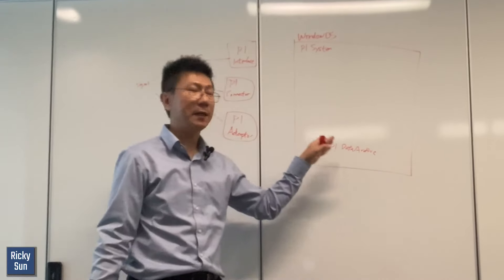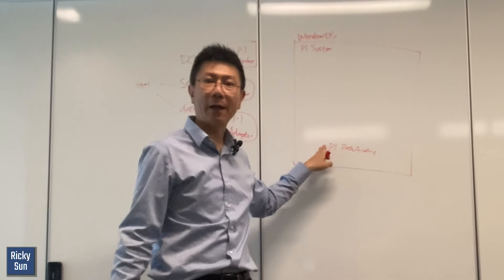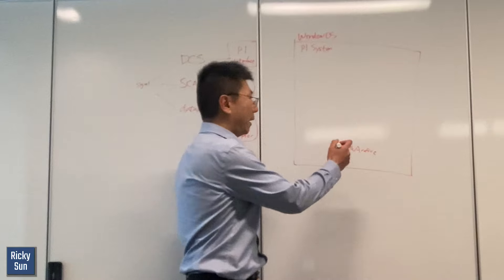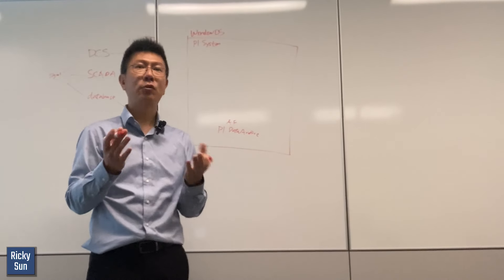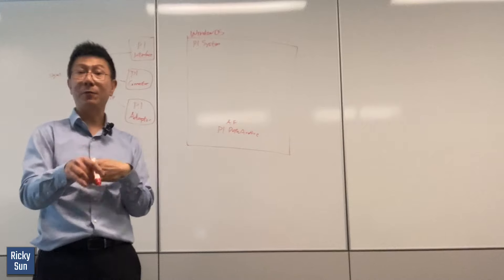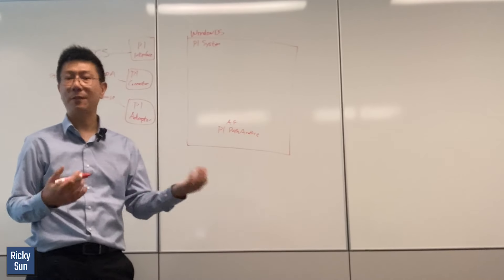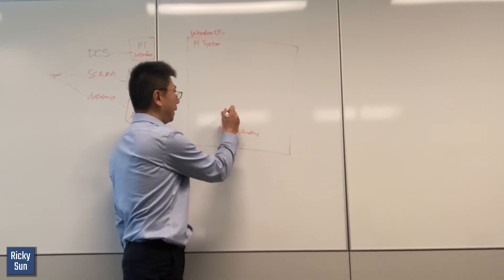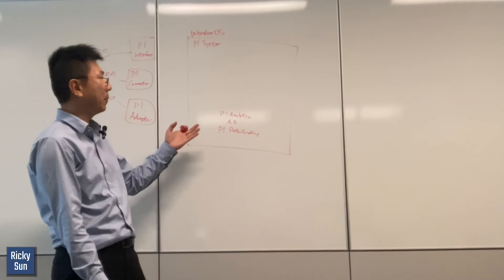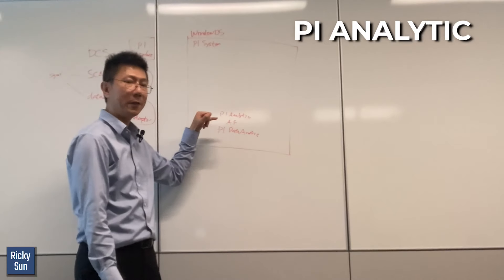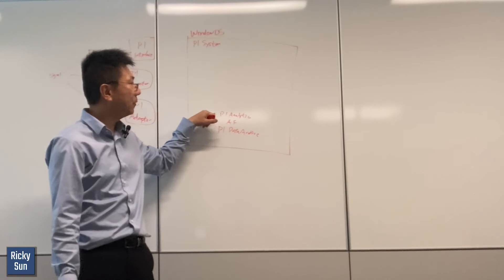The interface, connector, or adapter is responsible for sending the data to the Data Archive — the timestamp and the value. Then we have AF, the Asset Framework. AF lets you structure your data so you can find it more easily. You can create a customizable hierarchy that fits your needs. We also have PI Analytics, which lets you make calculations from the PI AF — you put data in AF and link it to the PI Data Archive to run analytic calculations.